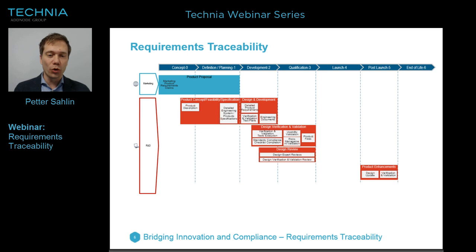And that goes through all the verification, validation, and test execution and support for that, where we actually handle the detailed tests and the test planning, as well as test execution, and can potentially drive that from Innovator. We also want to make sure that all standards are met, and we map the regulatory areas, say EMC requirements, to the standards and break those down into detailed requirements. And that's how we keep track of the requirements all through the type tests.